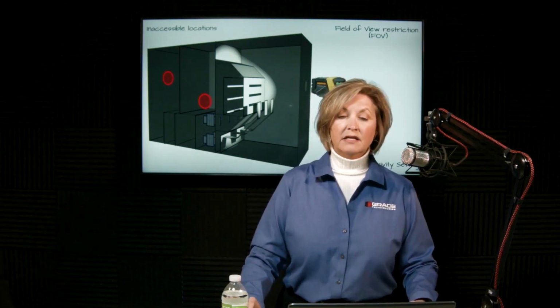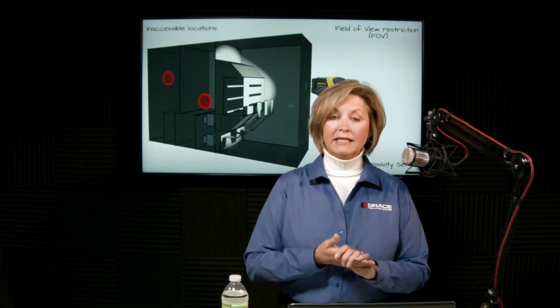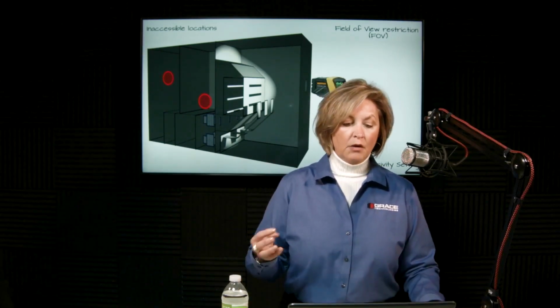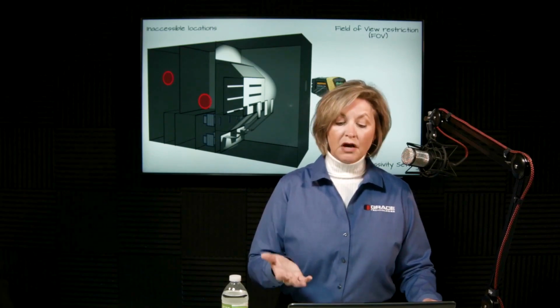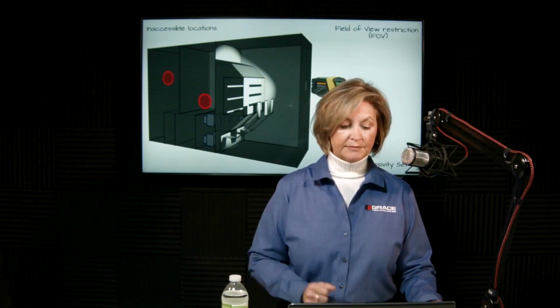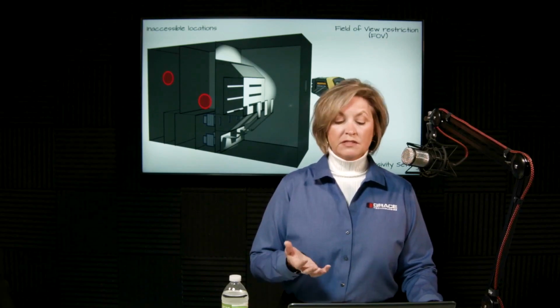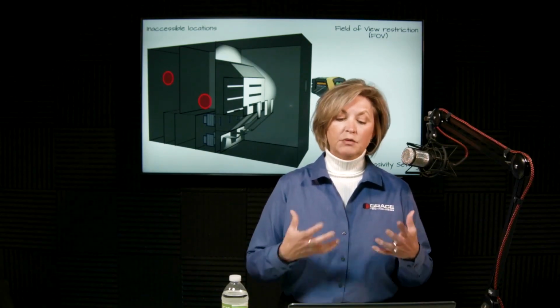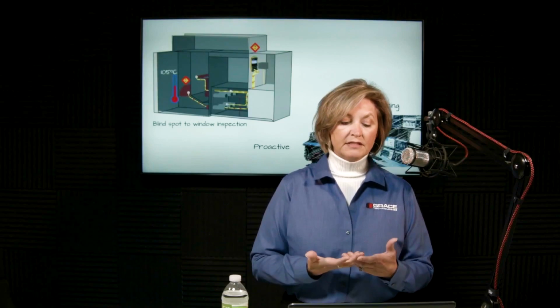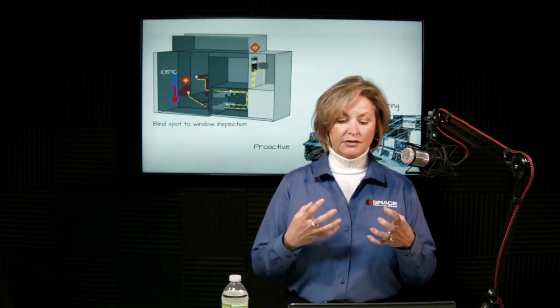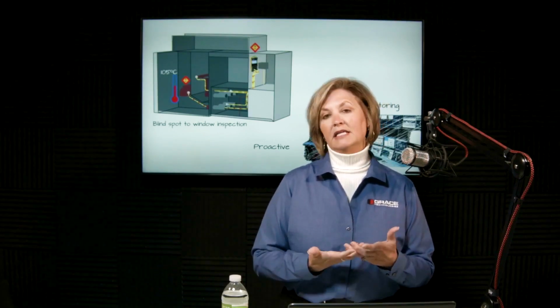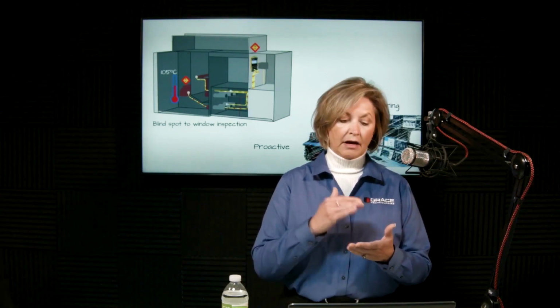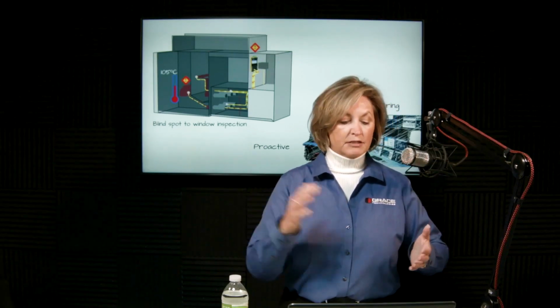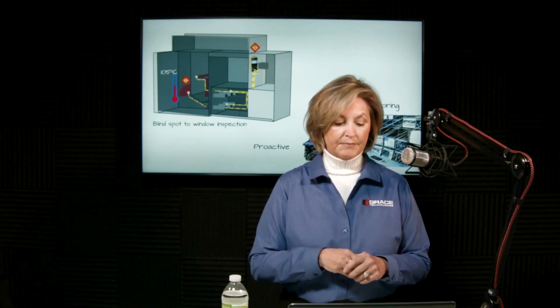Maintenance cost savings can be recognized by eliminating the thermal scan activity, which would allow more focus perhaps on other tasks during a turnaround project. That's why many facilities are deploying a full continuous thermal monitoring solution, not only to save maintenance dollars and gain relief of scarce human resources, but also to gain insight into the thermal baseline of each critical asset on site throughout the course of the year, especially during the peak loading times.